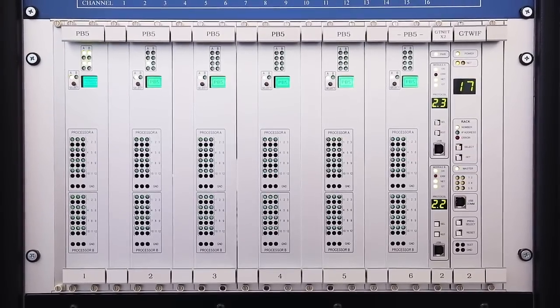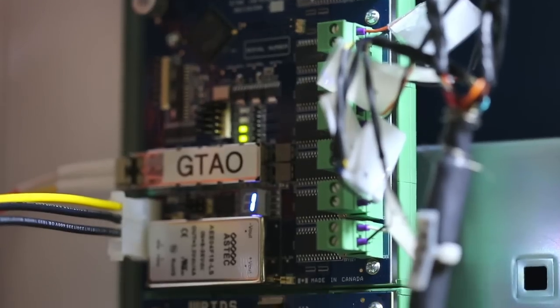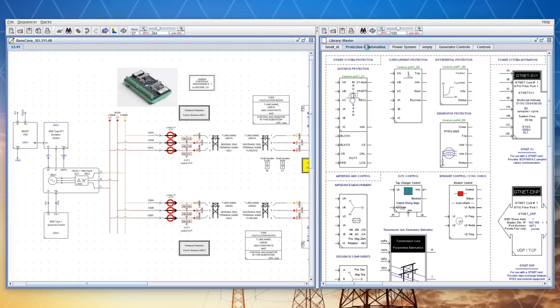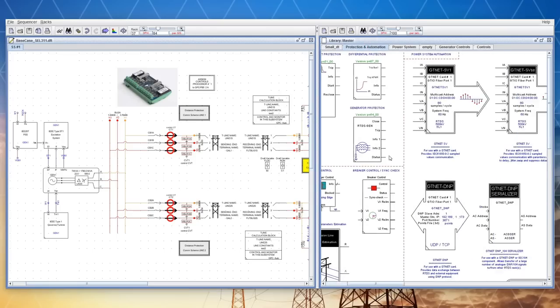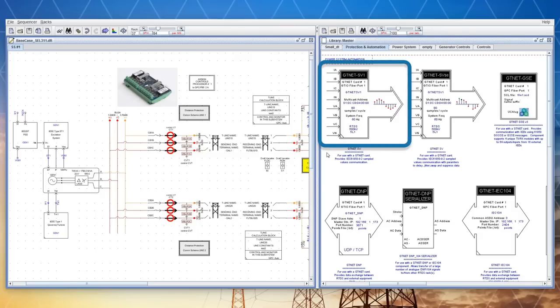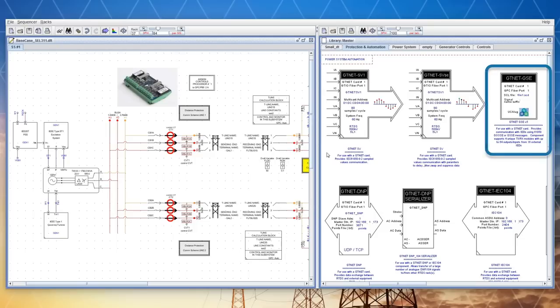As an alternative to using the GTAO card for analog output, the current and voltage signals from the simulation case could be sent to the relay using IEC-61850-9-2 sampled values data. The breaker commands and status could be communicated via IEC-61850-goose messaging.